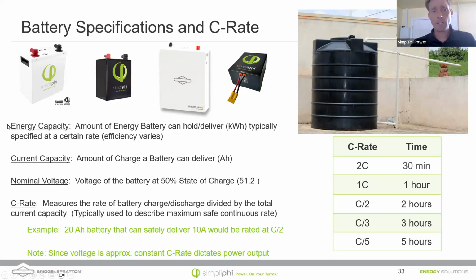So the energy capacity of our batteries is specified at a C/5 rate. That means if you discharge the battery over 5 hours, you'll get the energy rating of your battery in terms of energy output. So if you have a 3.8 kilowatt hour battery, you discharge it at 1.9 kilowatts. That would be a C/2 rating, right? You get a little less energy out of it if you discharge at that rate.